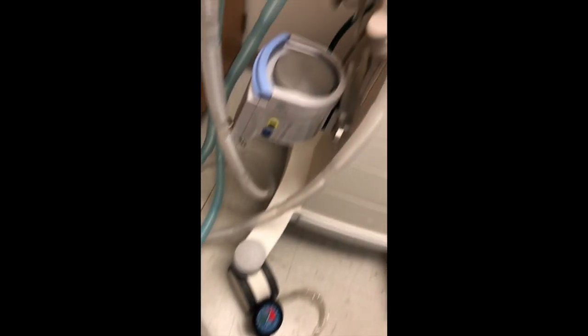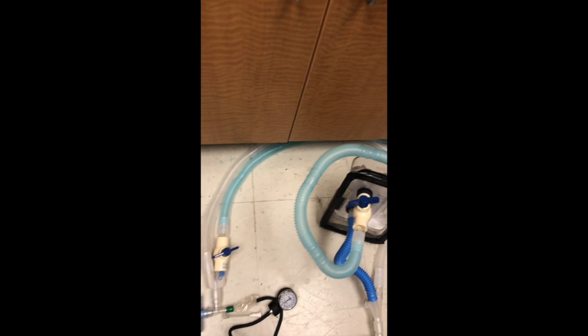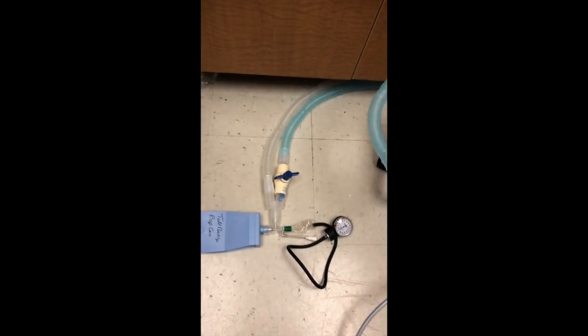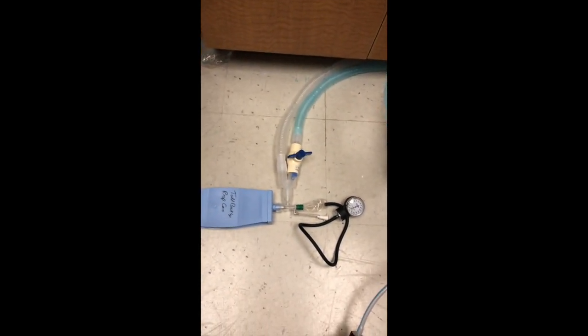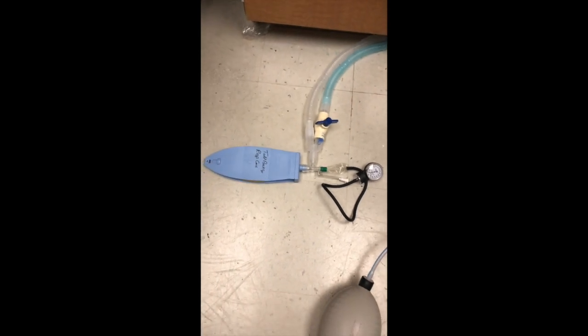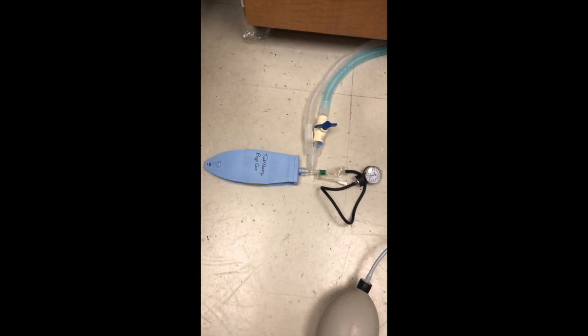The mercury gauge just has to be converted to centimeters of water, which is a very simple multiple. Here, if you see, this gauge is moving with each breath, and the PEEP is 8, which this is denoting, and it's going to a pressure of around 24, which is the peak pressure. So in real time, we can monitor the PEEP and the peak pressure. Now again, please note that this peak pressure is much less than the peak pressure set on the ventilator. So that is the key thing.